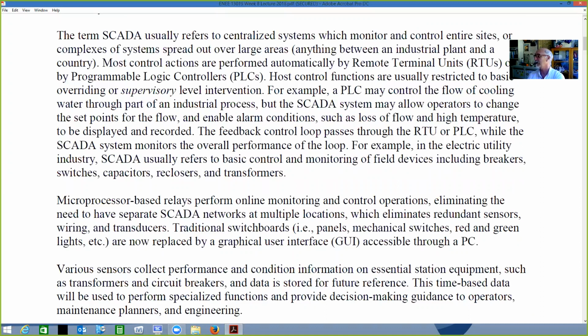For example, in the electric utility industry, SCADA usually refers to basic control and monitoring of field devices, including breakers, switches, capacitors, reclosers, and transformers. Microprocessor-based relays perform online monitoring and control operations, eliminating the need to have separate SCADA networks at multiple locations, which eliminates redundant sensors, wiring, and transducers.